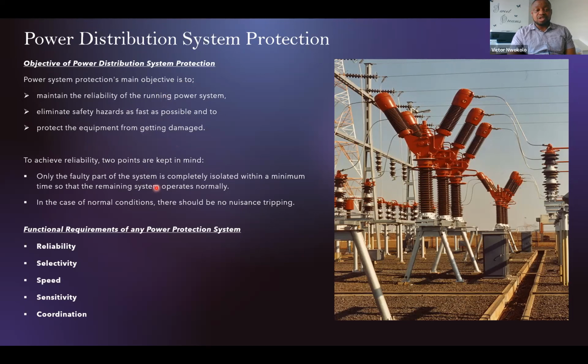And in order for us to achieve this, we have to keep two things in mind. We have to make sure that only the faulty part of a system is completely isolated within minimum time so that the remaining system can operate normally. We also have to keep in mind that in normal condition, there shouldn't be any nuisance tripping when we're designing protection against fault.